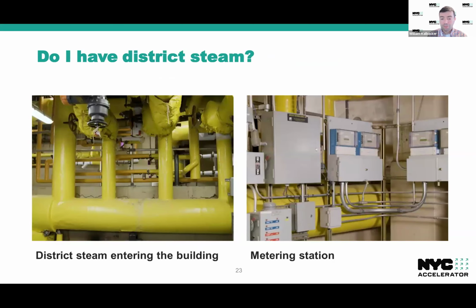But you might not have a boiler and you might still have steam. And one way to do that is through district steam. So Con Ed utility can produce steam off-site and send it to your building through a high pressure network. So it'll come into the building in the basement at high pressure. There'll usually be some equipment to step down the pressure before sending it to the building, but you will also see a metering station such as the one you see on the right here, which basically measures the volume of steam coming into the building.